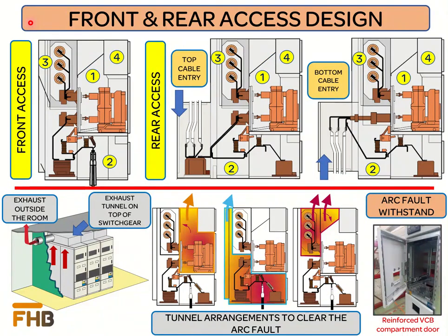Air-insulated switchgear can either be front-access design or rear-access design. This definition is according to the connection of the power cables in the switchgear. If the power cables from the field are connected at the front side of the switchgear, it is called the front-access design. In the front-access design, all the installed components are accessed through the front side of the switchgear and there is no need to access the switchgear from the rear side for maintenance purpose.